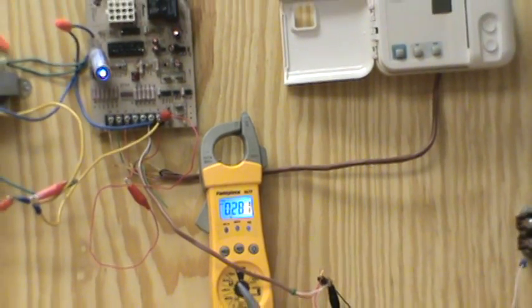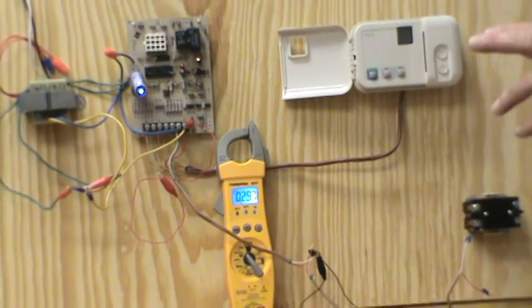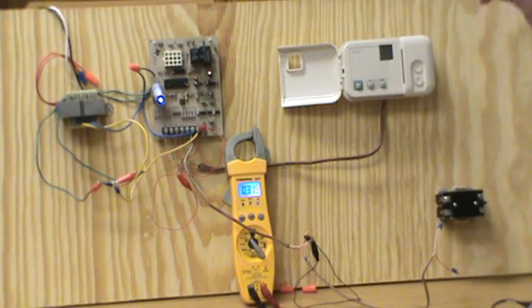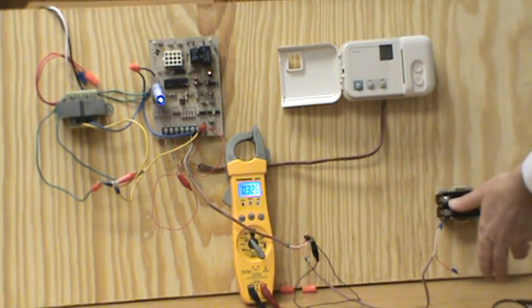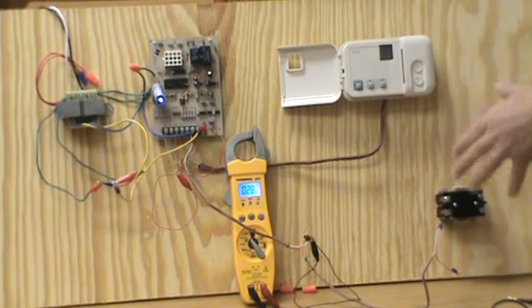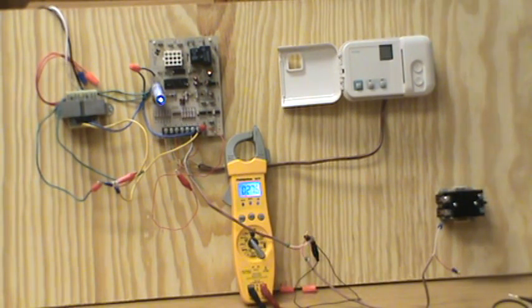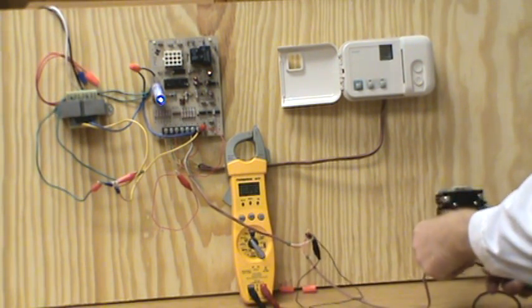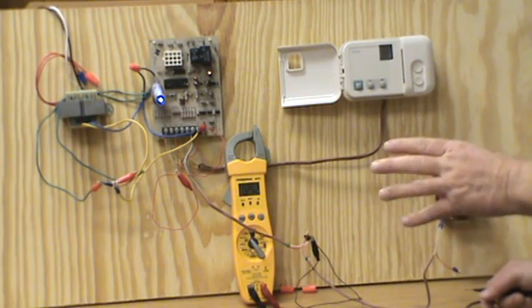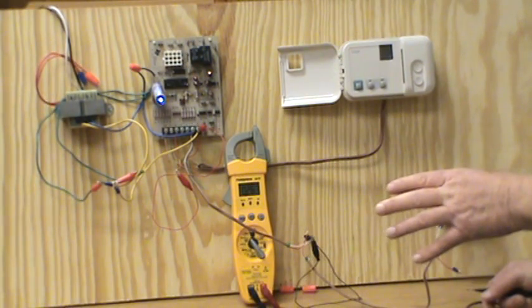Now that quickly, after you've isolated the short in the cooling circuit going outside, you disconnect the two wires at the condenser, check voltage, and there's none. So you know that the short is in the attic or in the wall somewhere. You didn't have to crawl around or anything. You went straight from the furnace to the outdoor unit without cutting power off, and able to check voltage and determine the fault is in the wiring in the attic or wall.